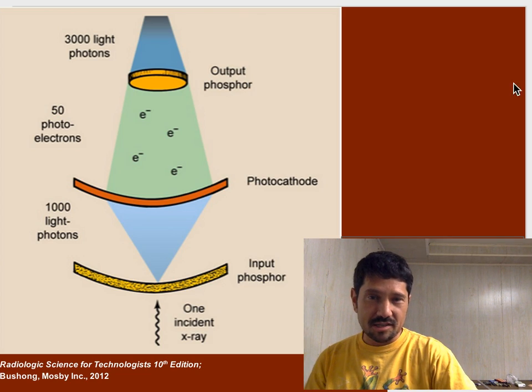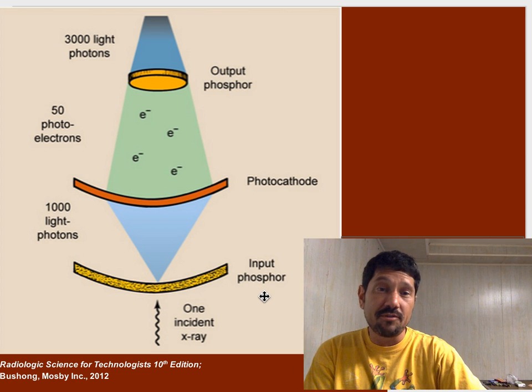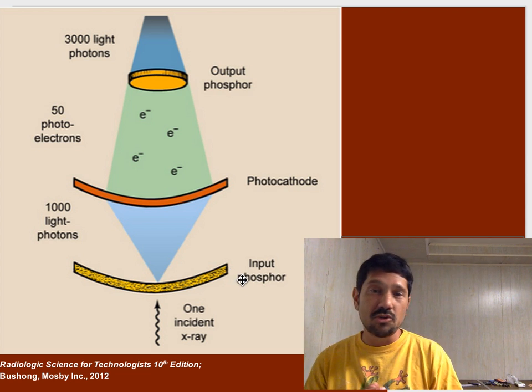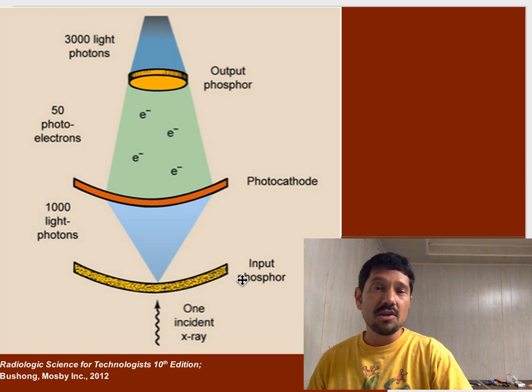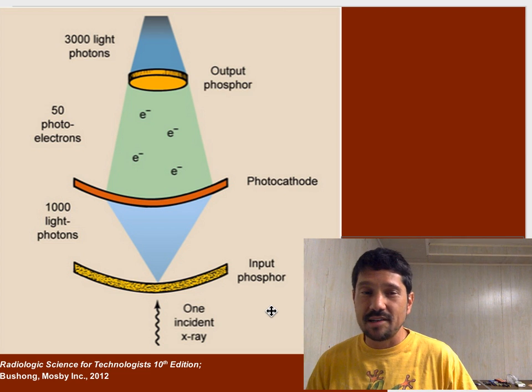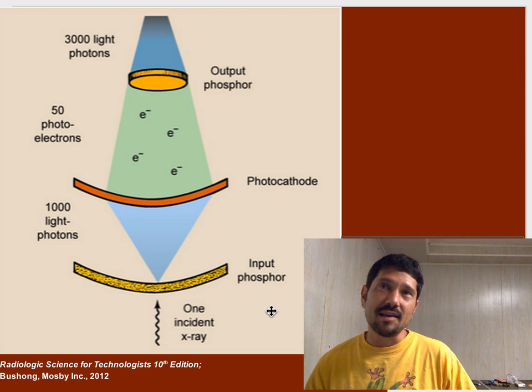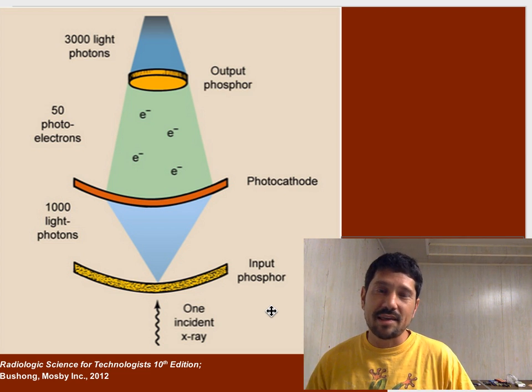Let's talk about our system. We have one X-ray coming in. It hits the input phosphor and it turns into a bunch of light photons. Because that input phosphor is our friend, cesium iodide. And it likes to absorb the X-ray and kick out light.